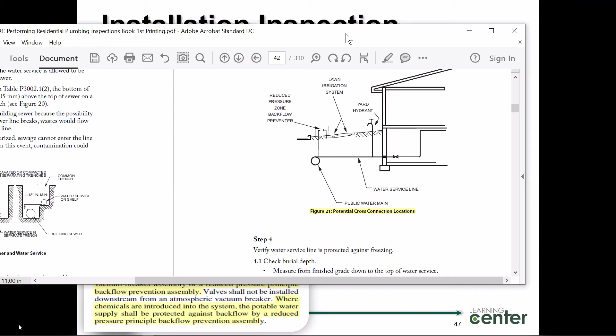Now, let's say, for instance, all of a sudden, we lose water pressure, ladies and gentlemen. The valves are open and maybe somebody's doing a little bit of work on the city water main, and all of a sudden I lose pressure. What's going to happen, right? This spring's going to slam shut, right? On zero pressure. Any kind of muddy, crappy water that's going to be flowing back, maybe under negative pressure perhaps, or maybe just flowing back, will go into this reservoir, and then the overflow will actually kind of seep around here and spill over, if you will, right? It's not going to go beyond this spring because the spring pressure is actually providing a seat here. So the water cannot go back down and contaminate the potable water supply, can it? Absolutely not. It can only spill over this particular dome on this particular vacuum breaker.